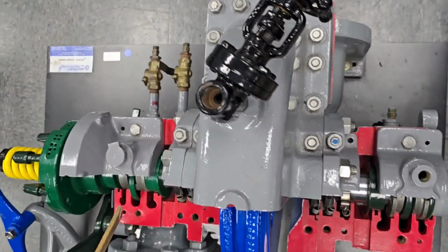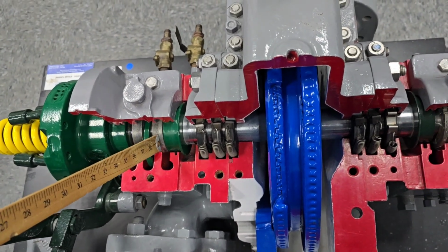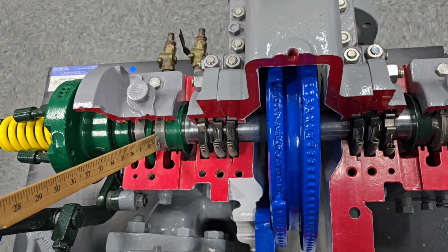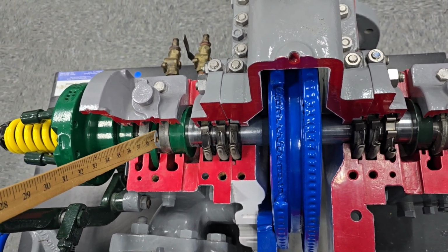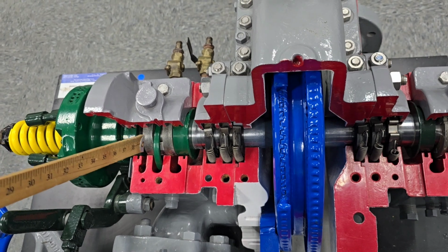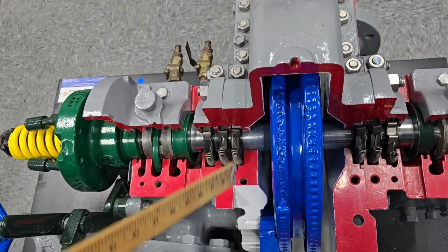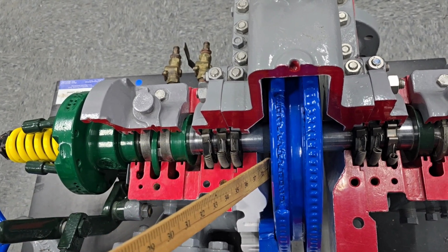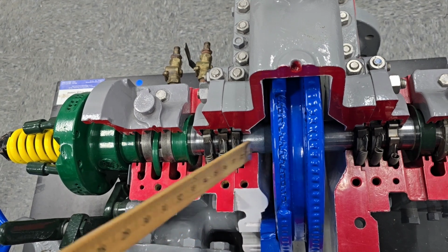Inside the bearing housing, you're going to have a set of bearings. The one that's located right here, closest to the rotor, is going to be your radial bearing. The radial bearing is going to keep the shaft aligned and reduce friction. It's also preventing movement in a circular motion. It's located closest to the rotor because this is the most amount of energy that's going to be exerted onto the shaft.